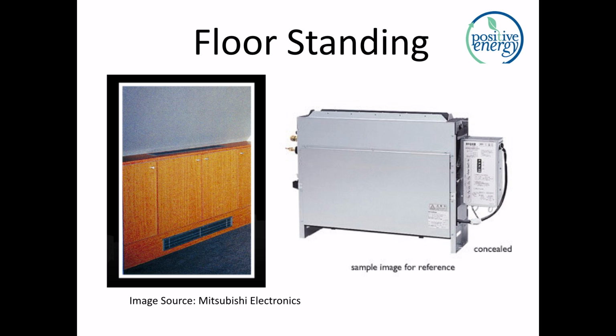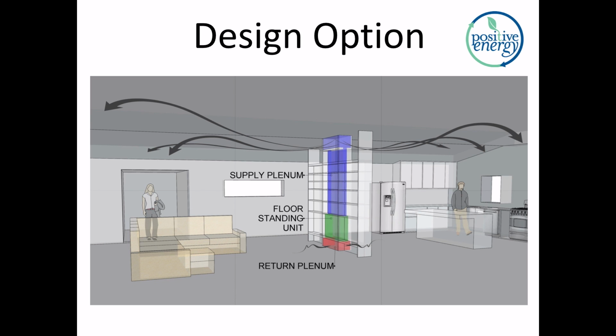Do not overlook the impact of these simple floor standing units. For instance, look here, we have a graphic of a return at the bottom, and we have the unit in there in green and our supply ducts going out the top of a built-in cabinet. So let's say you have a residential project where you have a flat roof assembly, or for whatever reason you don't want to put ducts in the roof, and you have this living room, dining room, kitchen, central core of the home, and you're not sure how you're going to deliver heating and cooling to it. Well, look, if you have this cabinet or you build in a site-built cabinet, you could deliver space conditioning to the center of this space, and all you needed to provide access for was refrigerant lines, condensate lines, and electric power. So very exciting opportunity, not to be overlooked.